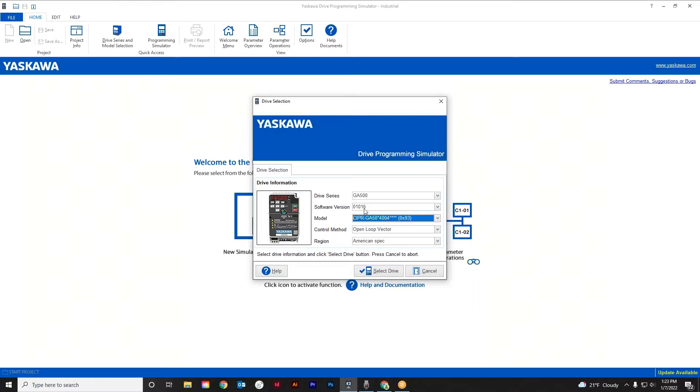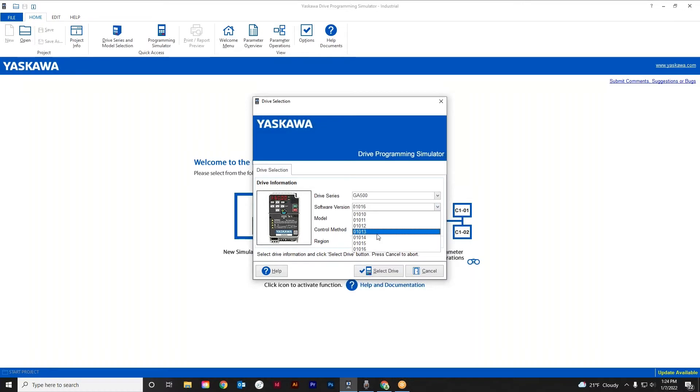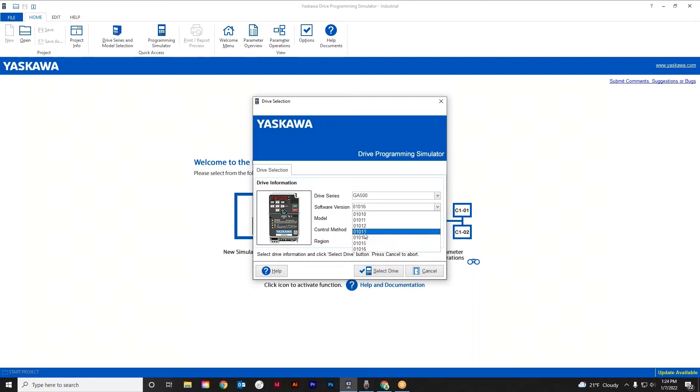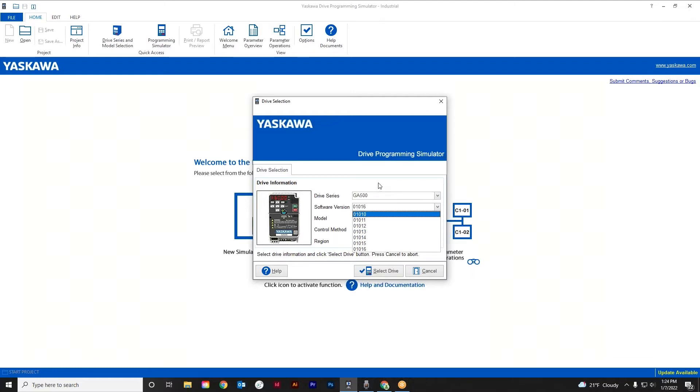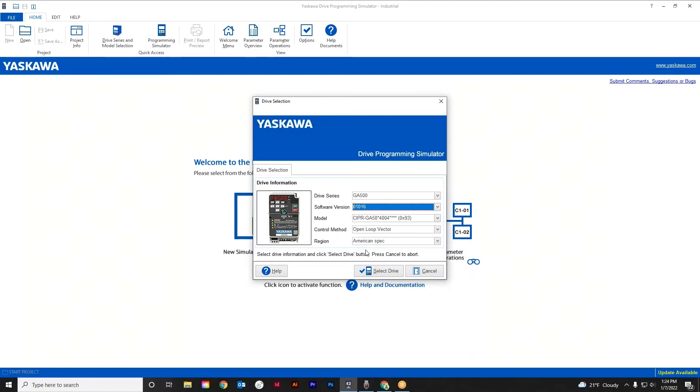Something else that's very important is this software version or firmware version, if you will, that's in the drive. So let's just say you actually have a drive there and you've received it. If you looked at the sticker on the side of the drive and it has software version, whatever, you can actually drop down and pick that version to match what you physically have there in your facility. Because this is important, because sometimes these older versions will have newer features, older features that are limited to that particular firmware or software version. So it's nice to marry this software version to what you actually have. And that number is actually located on the side of the drive. It's on the white sticker. It's called a PRG number, Paul Robert George number, and that's what you want to match up with this. I'll go with 16 because that's the most recent one.